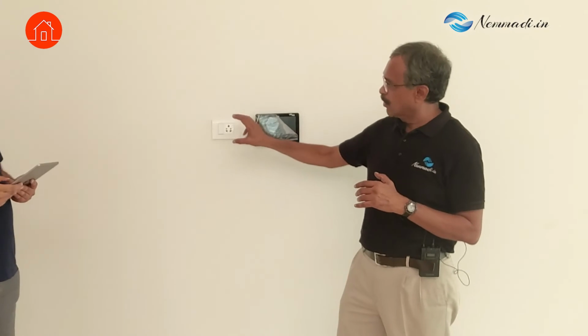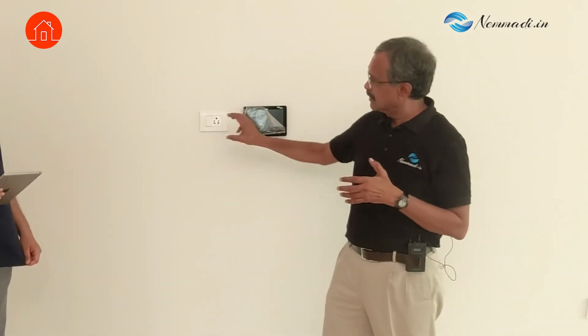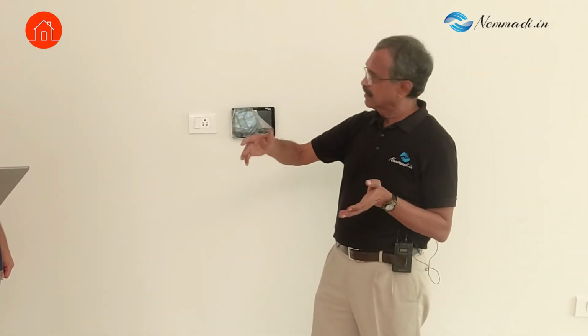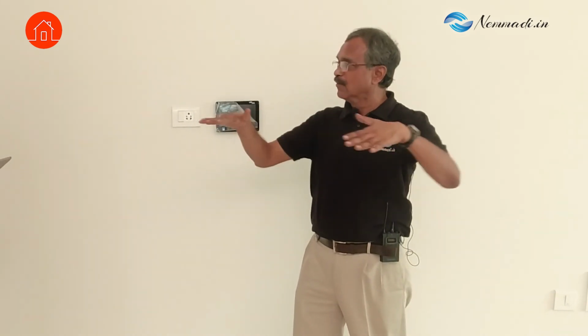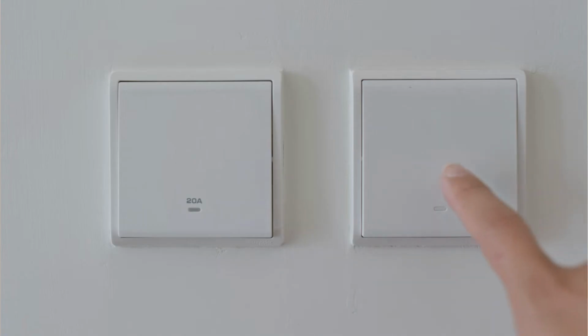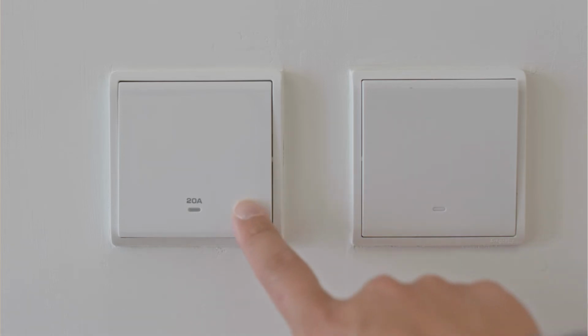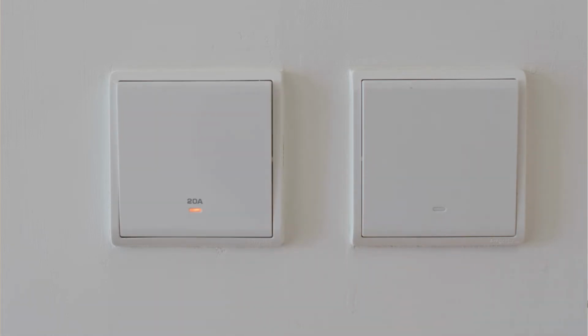One more thing is, the normal defects we notice are with the plates, as Uday was mentioning, not only the gaps, sometimes the alignment is not okay. They are not horizontal, and usually the switches provided should be in one plane. Otherwise it looks ugly, especially if the switches are side by side. They should definitely be at one level. Up, down, or even tilted looks odd. We point out all that.